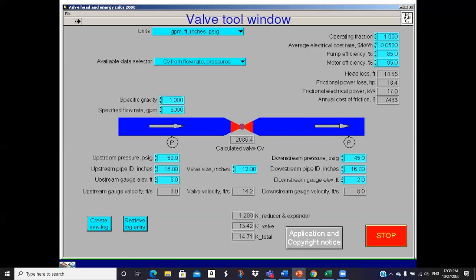And then we get a K value, the loss coefficient for the expander and the reducer, because we've got to get from 16-inch to 12 and then from 12 back to 16. We get a K value for the valve itself. And we also get a K value total, which is just the sum of those.